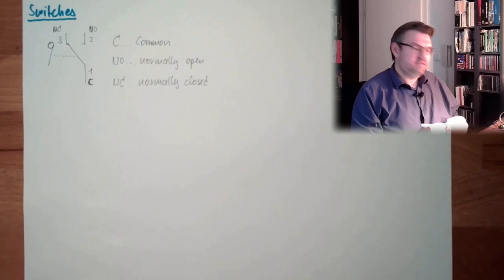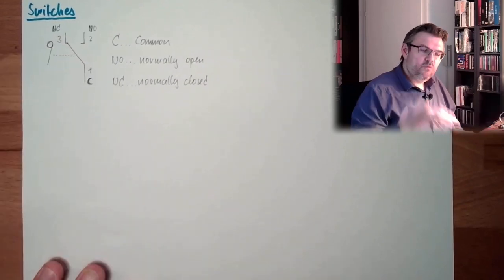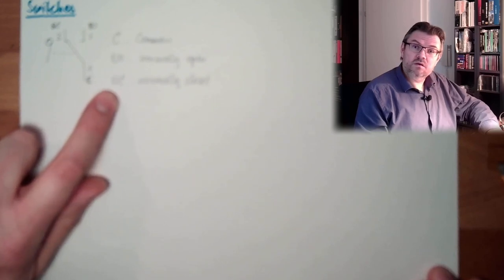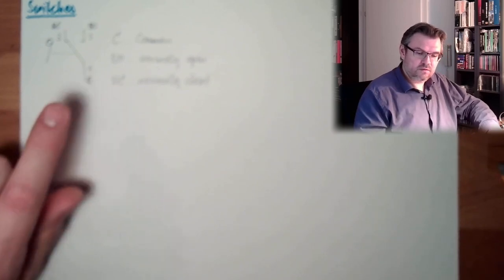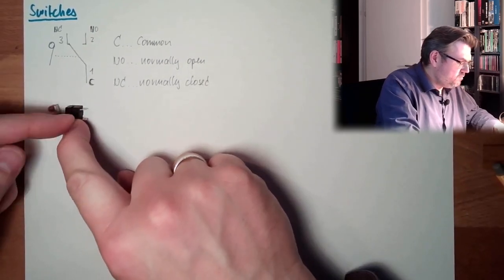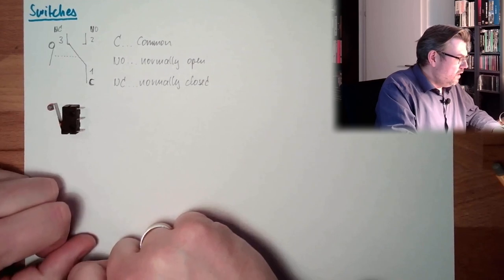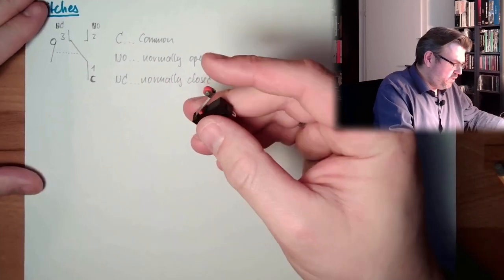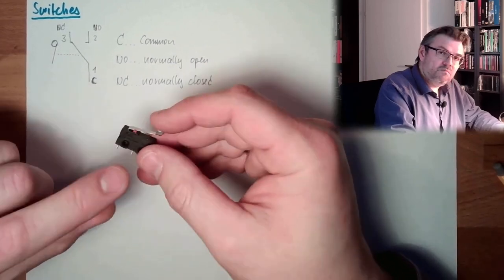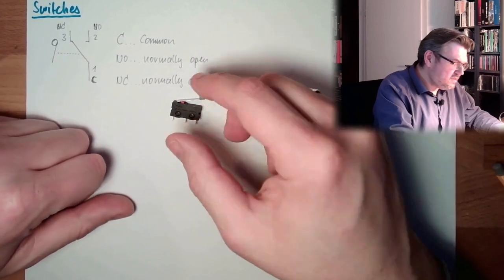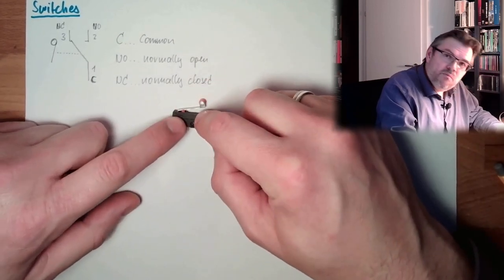Some do only have two contacts. Then it's usually a normally open contact. When you push the button, then it's closed. But there are also switches which are only one normally closed contact. Emergency switches are usually like this. They are normally closed, and if I operate, they are open. Here we have the C, common. So that's a mechanical switch, mechanical. Because there is really some sheet of metal in there which is operating the thing. It's really operating.